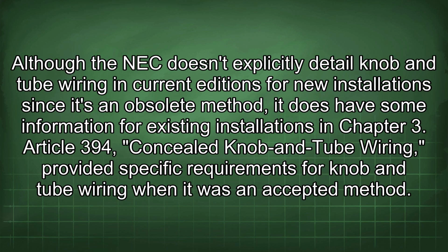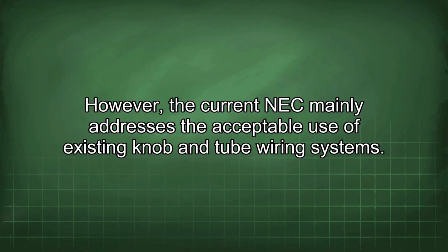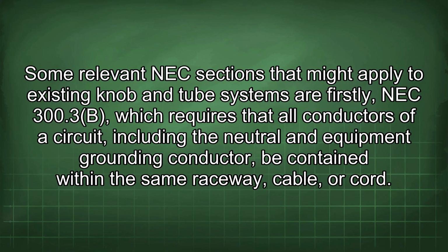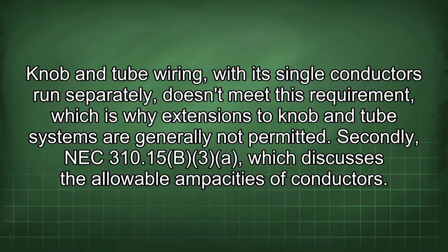Although the NEC doesn't explicitly detail knob and tube wiring in current editions for new installations, since it's an obsolete method, it does have some information for existing installations in Chapter 3. Article 394, Concealed Knob and Tube Wiring, provided specific requirements for knob and tube wiring when it was an accepted method. However, the current NEC mainly addresses the acceptable use of existing knob and tube wiring systems. Some relevant NEC sections that might apply to existing knob and tube systems are, firstly, NEC 300.3(B), which requires that all conductors of a circuit, including the neutral and equipment grounding conductor, be contained within the same raceway, cable, or cord. Knob and tube wiring, with its single conductors run separately, doesn't meet this requirement, which is why extensions to knob and tube systems are generally not permitted.